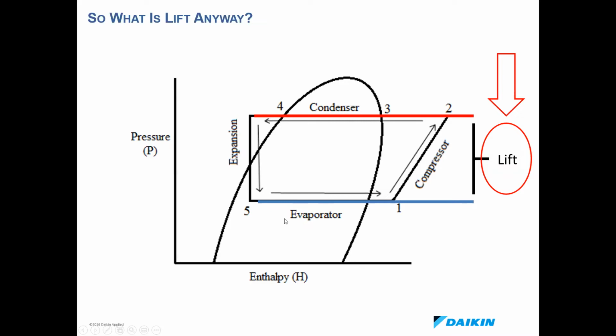And then the evaporator, this blue line, is going to be your leaving water temperature set point of your evaporator. So that difference is going to be your lift. And your compressor is what's doing that duty. It's getting that refrigerant pressure up to that condensing pressure for the unit.